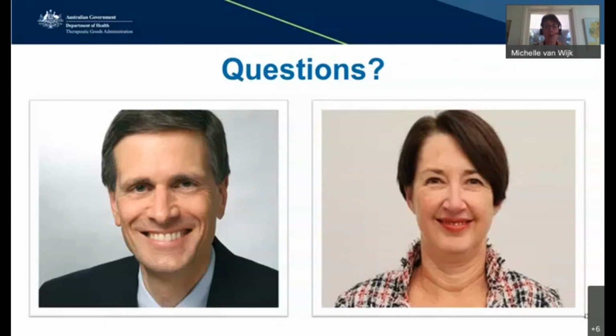Will the UDI be applicable to software that is a medical device, such as EMR? I think the answer is yes. If it's regulated as a device, it will also require a device identifier, and that's similar to what other countries have already implemented.